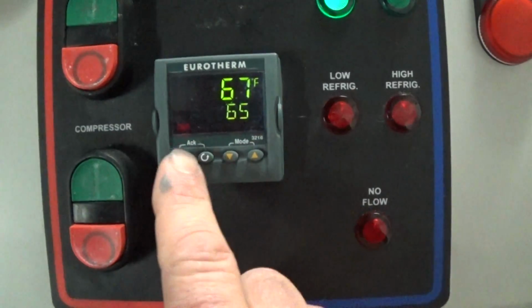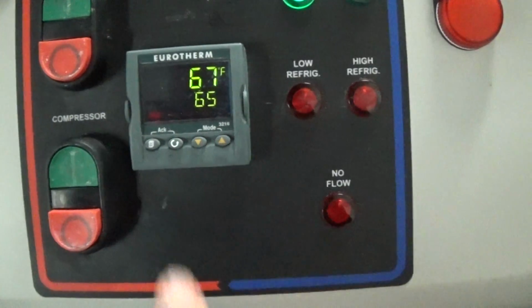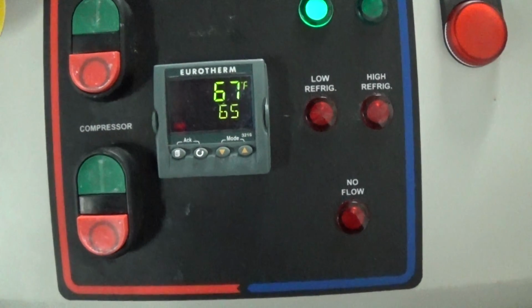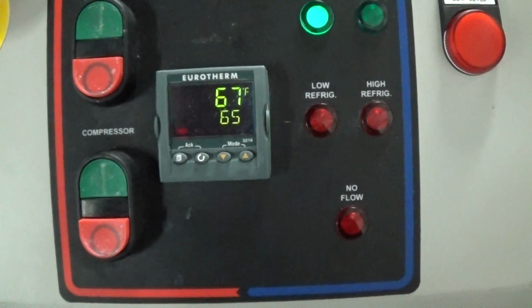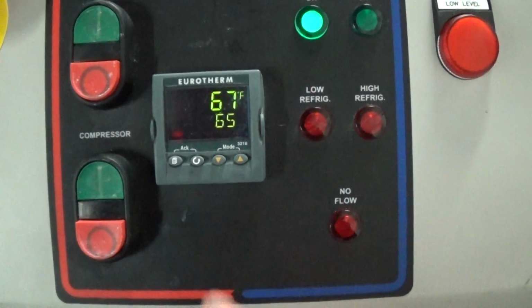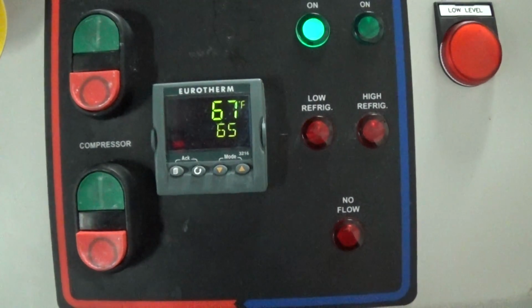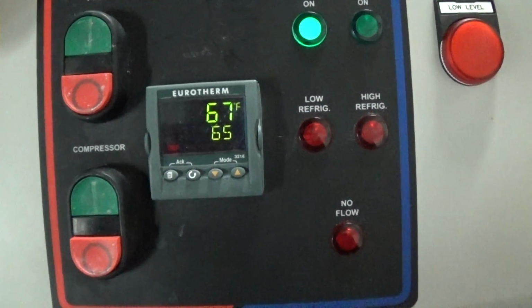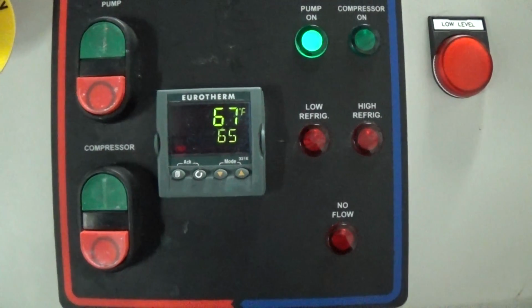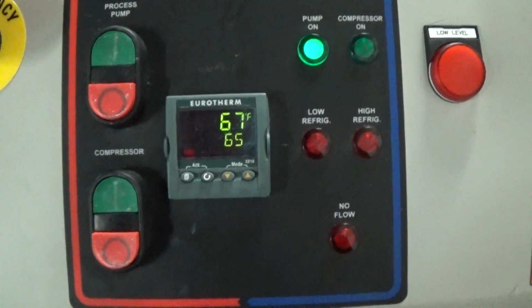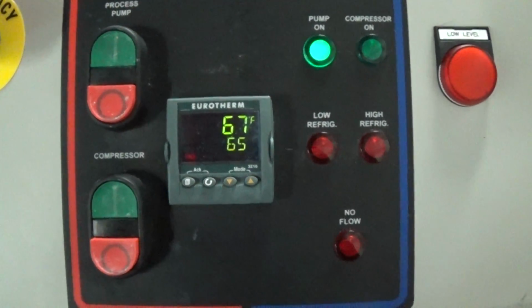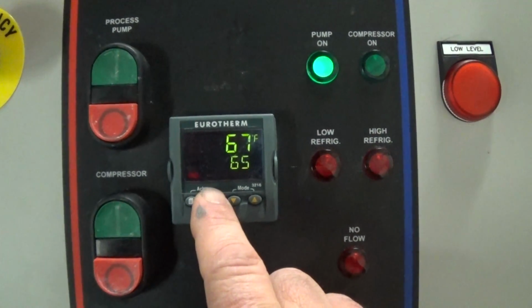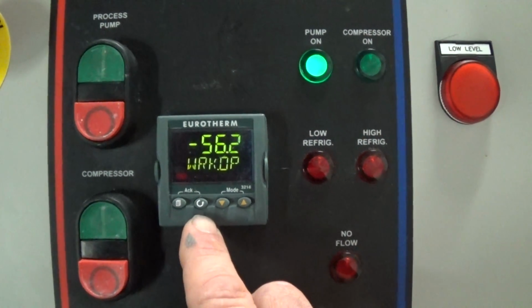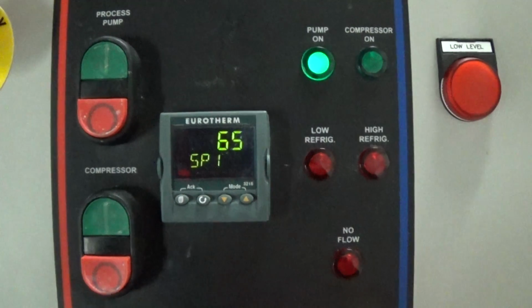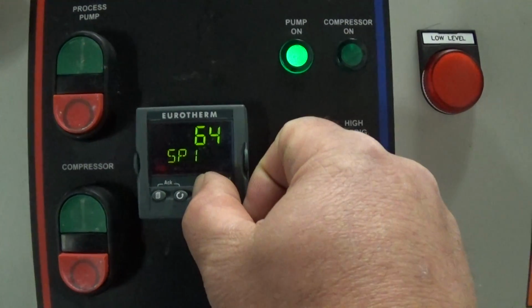A couple buttons here. All you have to worry about is this little circular looking thing. And all we'd really worry about is set point 1. This has a range of 50 to 65 Fahrenheit. It can be changed if you call up the factory. You can speak to Dave there. We wrote the numbers on the contact information on the pages that are going to be in the control cabinet here. But all you do is you press this once. You go by this, the WRK page. Press it twice. That brings you to set point 1.